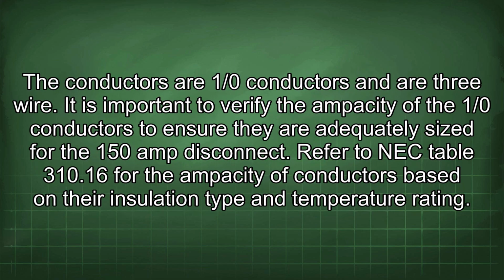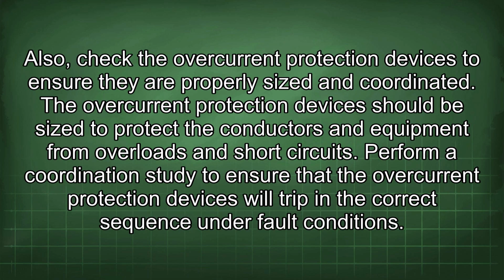The conductors are 1/0 conductors and are 3-wire. It is important to verify the ampacity of the 1/0 conductors to ensure they are adequately sized for the 150 amp disconnect. Refer to NEC Table 310.16 for the ampacity of conductors based on their insulation type and temperature rating. Also, check the overcurrent protection devices to ensure they are properly sized and coordinated. The overcurrent protection devices should be sized to protect the conductors and equipment from overloads and short circuits.